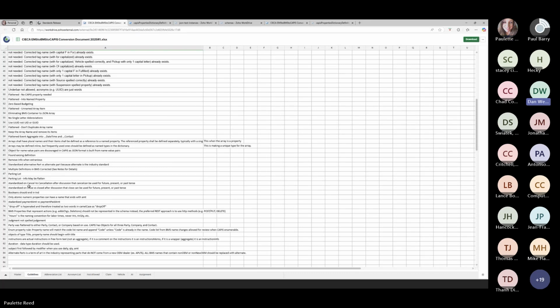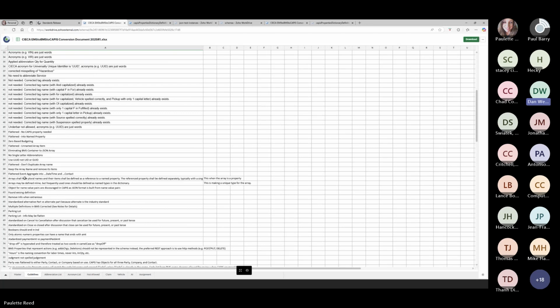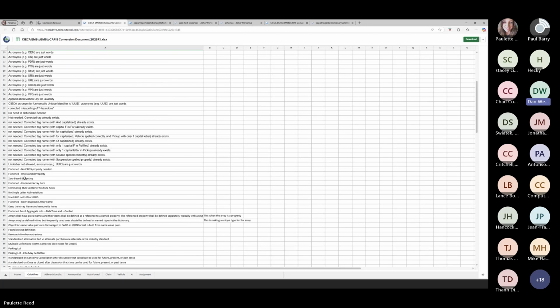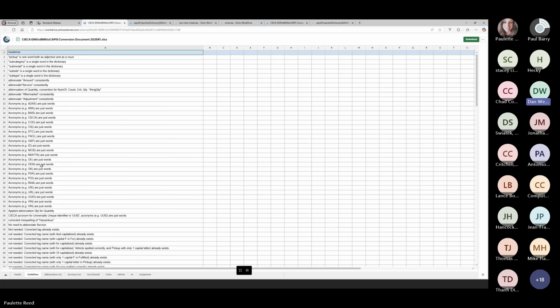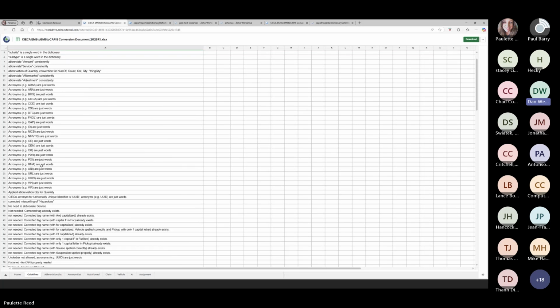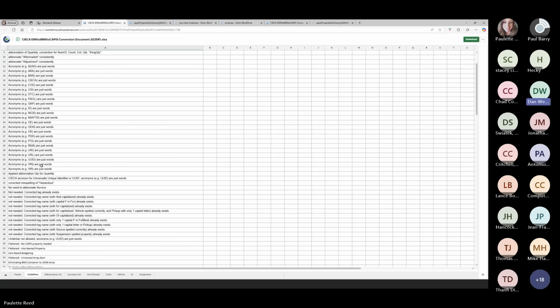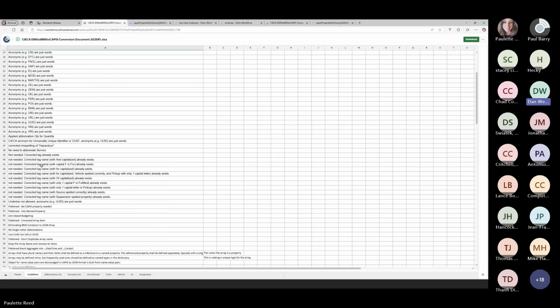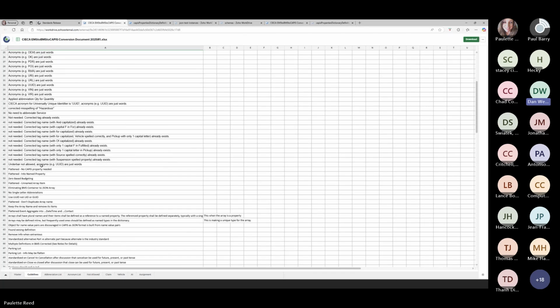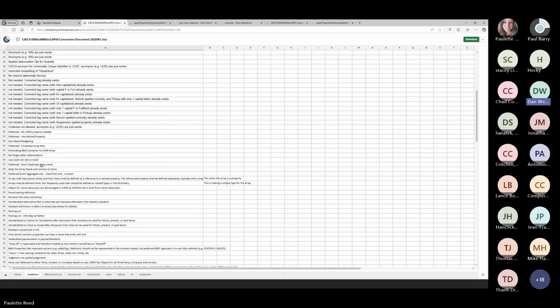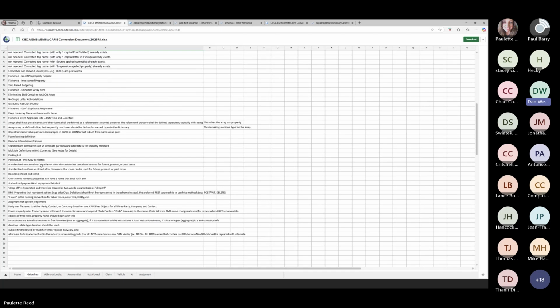One of the things that started this right off the top was that the tags, as you're familiar with them, are a bunch of common words in English that apply to our industry, all mashed together into one identifier. We found that over the years in BMS, some of those words we mashed together were misspelled. So we made a rule that the only things that can be in a tag are a correctly spelled word, an accepted acronym, or an accepted abbreviation. We'll see changes here because we had to match an acronym the industry likes to use, or we've standardized on an abbreviation.